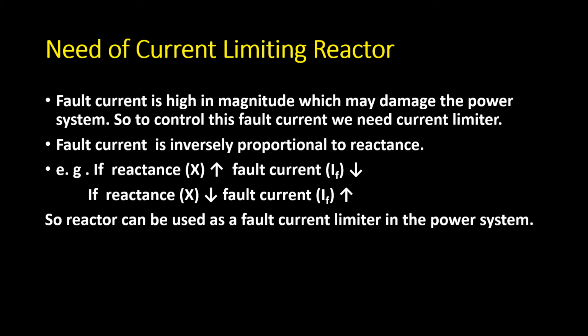If no step is taken to limit the value of short circuit current, it may damage lines and other equipment connected in an electrical power system. And we also need very heavy duty circuit breakers. So in order to limit short circuit current, additional reactance is inserted in series with the system at suitable locations.